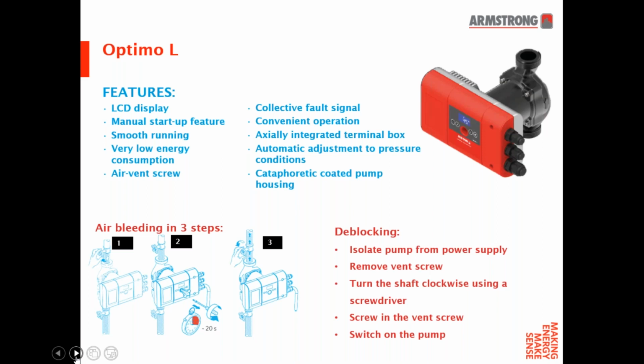So it's the screw in the middle: isolating the pump with the upper isolation valve, unscrewing the screw slightly for up to about 20 seconds, and then opening up the isolation valve that you've closed off before the operation. Again, deblocking, exactly the same as before. Isolate the pump from the power supply, remove the screw vent, turn the shaft clockwise using the screwdriver, screw in the vent screw, and switch the pump back on.